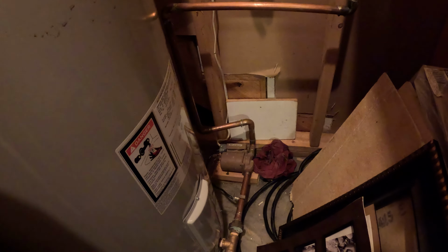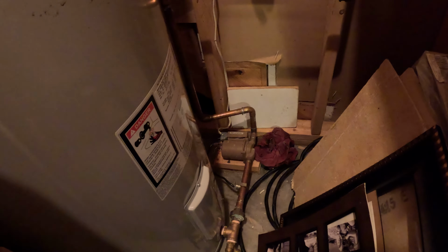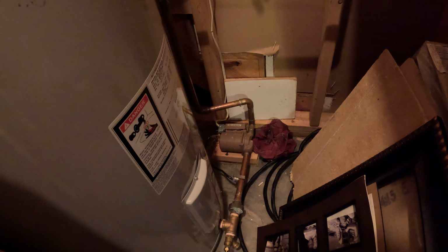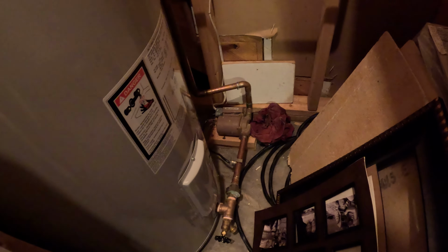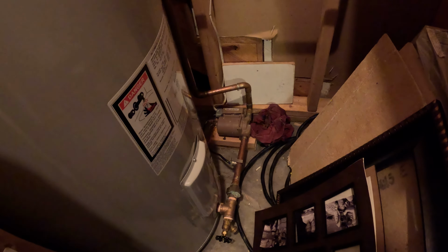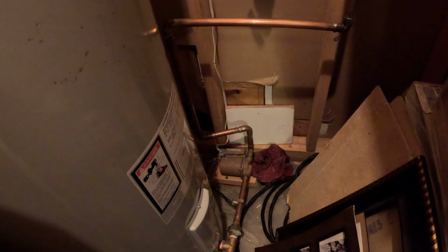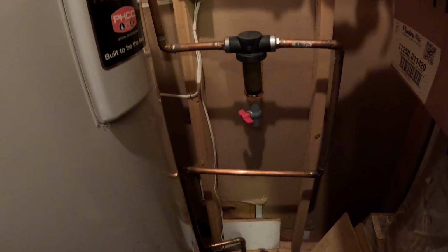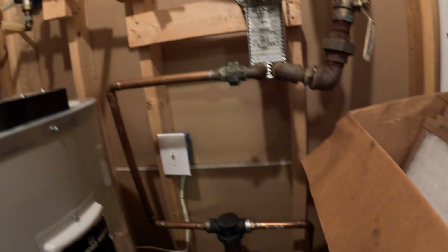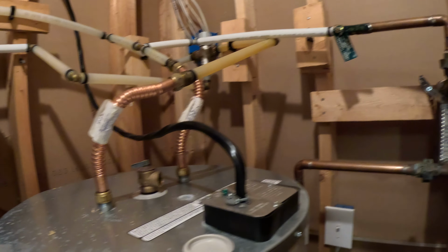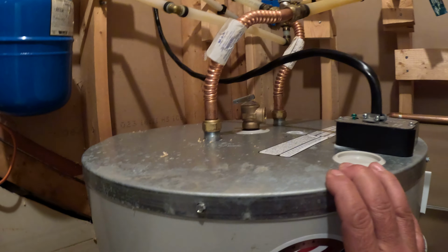There's a circulator pump at the very bottom. It's basically monitoring the temperature. You can see that thermocouple that's on that. It's just a switch you buy and tie into the pump, and when the temperature of that pipe reaches a certain level, it kicks that circulator pump on, which takes the cold water from the bottom of the hot water heater, circulates it through the heat exchanger, and then it's fed back into the hot water heater.